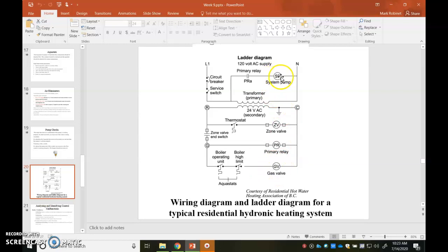The pump is already running. What will happen here is as soon as we get to 180 degrees, this boiler operating aquastat opens. The high limit stays closed because it's not at 200 degrees, and it'll cut the power to the gas valve. This boiler operating thermostat aquastat will open and close as the heat gets dissipated from the water. Meanwhile, the pump runs all the time, the thermostat's still calling for heat, and the zone valve is open. So this allows the water to go through the system.